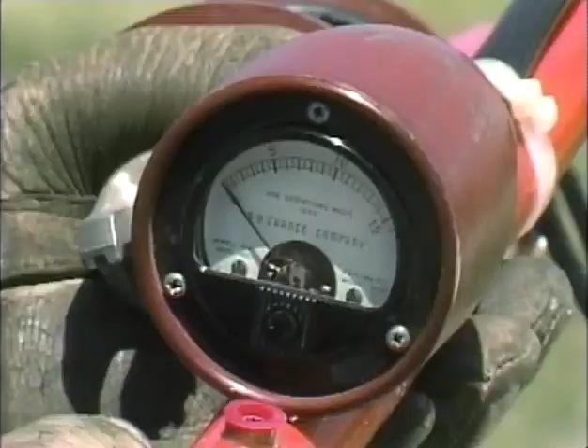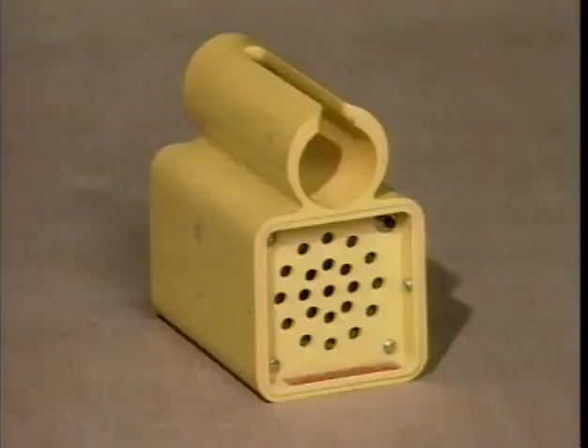And to test a circuit properly, you should use a tester on all the lines at the immediate work site. Discovering one line in a circuit is dead is no indication of the status of other lines. Under certain conditions, one line may be dead while other lines on the same circuit may be live. So it's important to test each line to confirm that the circuit is de-energized.